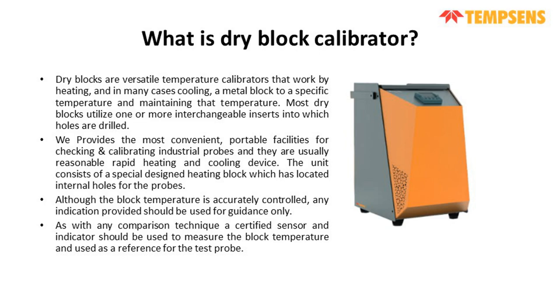These calibrators have a metallic insert with holes according to the customer's needs, and it can comprise around 4 holes to hold your sensors. It is used for the calibration of RTDs and thermocouples. Dry blocks are versatile temperature calibrators that work by heating and, in many cases, cooling a metal block to a specific temperature that is maintained, and it has interchangeable inserts that can fit into those holes. They are accurately controlled by PID controllers, and the accuracy and stability are very good, and that's how we can calibrate the RTDs and thermocouples.